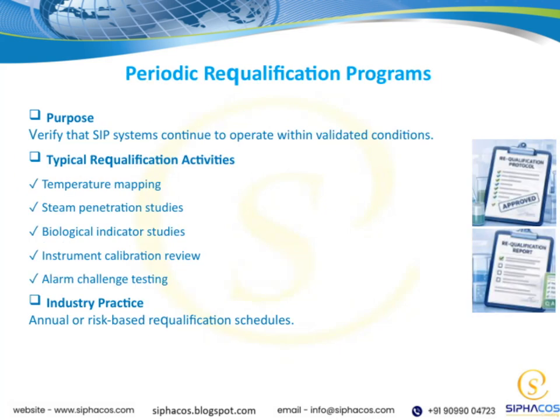Let's talk about periodic requalification programs. They're all about making sure our SIP systems keep working exactly as they should, within their validated conditions. To do this, we run a series of checks: temperature mapping, steam penetration studies, biological indicator tests, instrument calibration reviews, and alarm challenge testing. These activities help us catch any drift or issues early. Typically, these requalifications happen annually, or more often if the risk calls for it. It's a vital part of maintaining system reliability over time.